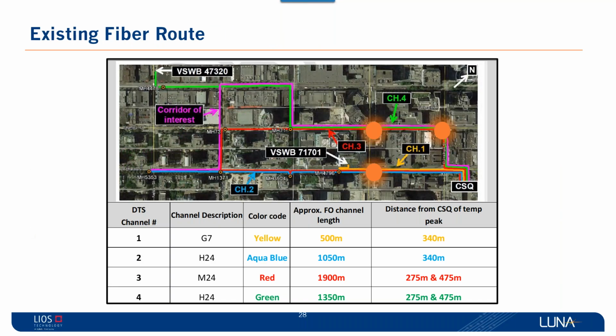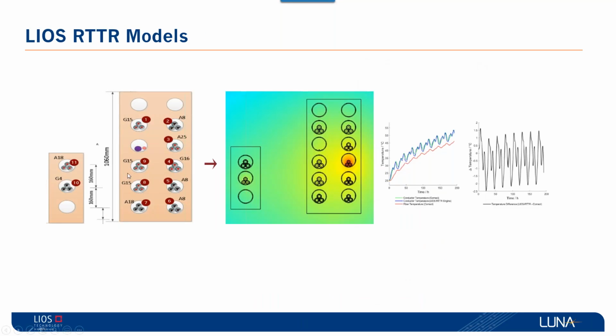The client cannot necessarily control the steam lines because they belong to another utility. This is not the same project, but a different project. But what was very important here is that you can see the different routes. Using the telecom fiber, you can actually understand how the duct bank is looking thermally first. What gets more exciting is that we can take that duct bank information, get the drawings from the customer, and pull that into our system.